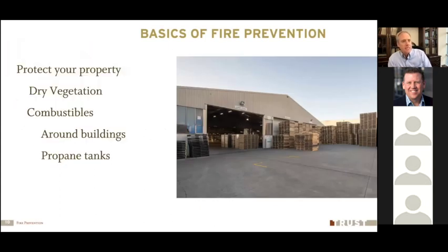Another common problem that we see is when we have combustibles close to the building. And this is an area where you can actually build in some protection against some of the external problems. If you have a lot of cut combustible materials like stacks of lumber and wood, old pallets, cardboard, right up close to the building. It could even be a dumpster that has a bunch of combustible material in it that is right up against the building. That's an opportunity for the arsonist to get in there and start a fire that could take down your building real easy. And even if it's not the arsonist, it could be an accidental fire, whether that's man-caused or some other condition that gets that material burning and could cause that loss to your building.